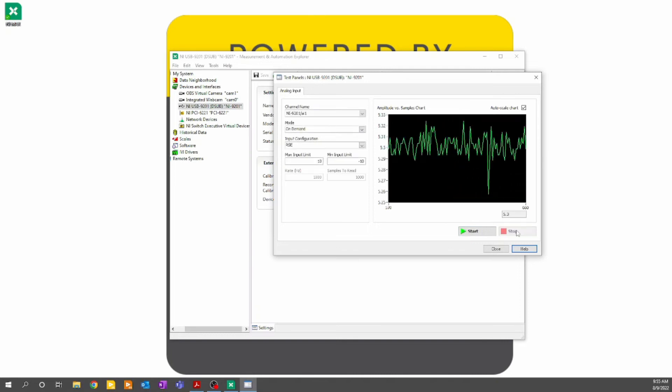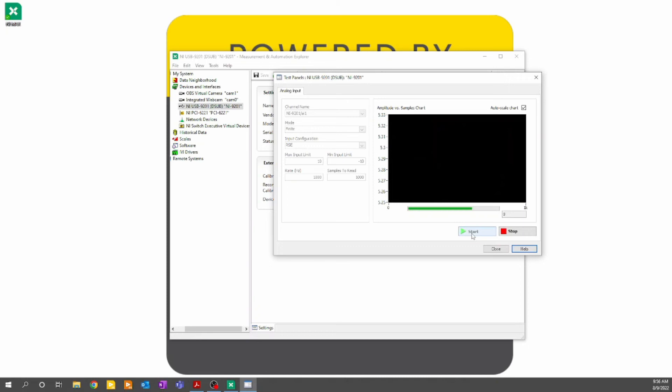To show functionality for some of the other options, if you click finite, it will gather samples to read samples at rate sample frequency. So this will acquire 1,000 samples at 1,000 hertz or collect data for one second. If I hit start, it will do the acquisition and then show me the data as a result.